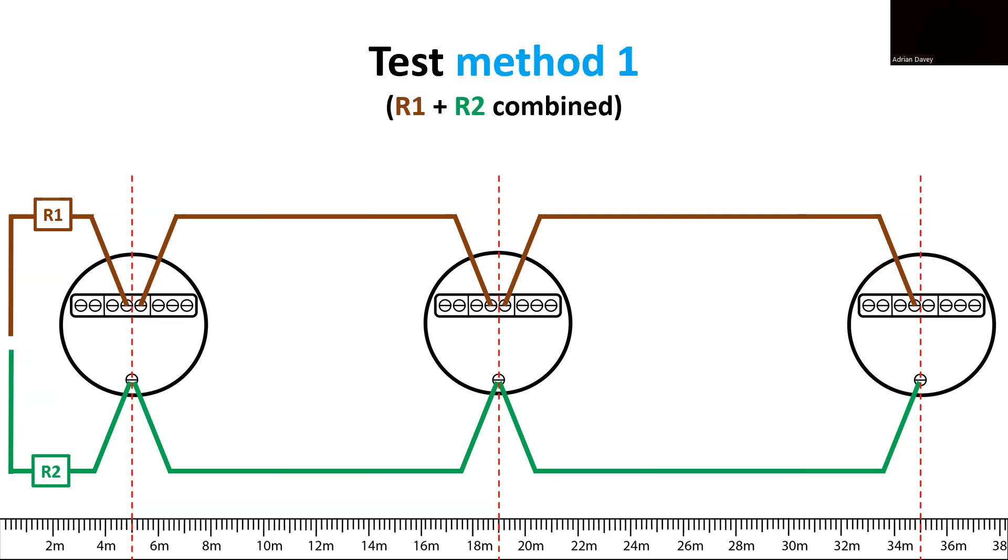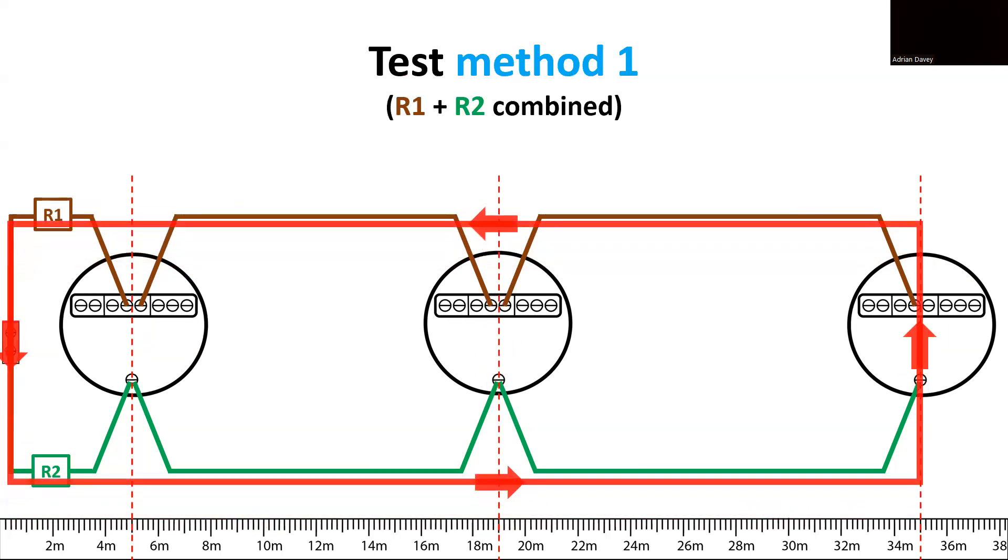For the low resistance tests, we'll be using test method 1, which allows us to measure and confirm both the R1 and R2 conductors simultaneously. It's like getting two tests for the price of one. We connect them together at a connector block at the supply end of the circuit, and then when we test between the line and CPC at any point in that circuit, we establish a probe loop, which verifies that segment of the circuit. Since we'll be conducting tests at each light point, we'll create three loops: here, here, and here.